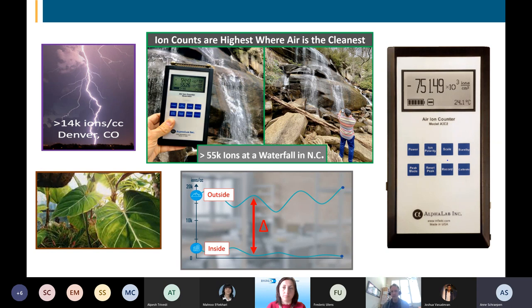It's important to understand no airflow, no ions. And it's important to understand that the higher the ventilation rate effectiveness in the space, the better the ions can mix with the contaminants in the space, the better results you should have. Another thing that's important to understand is that you may be emitting a high concentration of ions at the register or grill in the space. And then you'll take your handheld ion counter into the center of the space and you may see diminished concentrations. The problem is simply that those ions that have been emitted to the space are working on the contaminants that are there. They're being dissipated. And over time, as those contaminants are removed, the ion concentrations, the residual ion counts, will increase. So that now when you walk in with your handheld ion counter in a steady state space that has been cleared of certain contaminants, you will read higher ion concentrations over time.